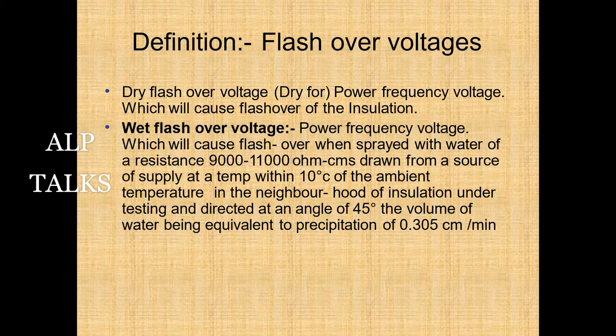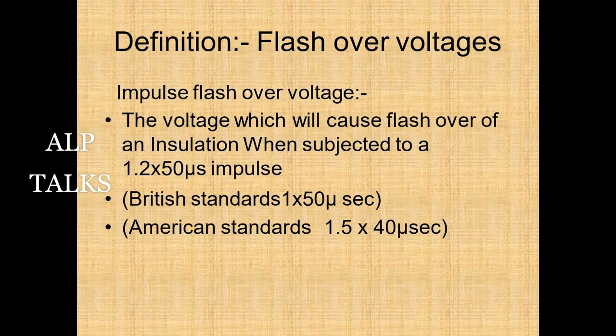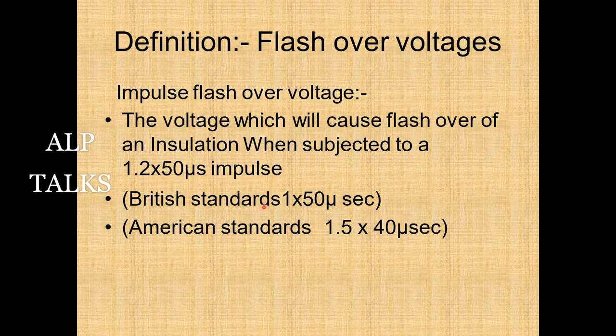Impulse flashover voltage is the voltage which will cause flashover of an insulation when subjected to a 1.2/50 microsecond impulse wave — that is the front and tail duration. The British Standard specifies 1.2/50 microseconds and the American Standard 1.5/40 microseconds, but generally 1.2/50 is the accepted standard.